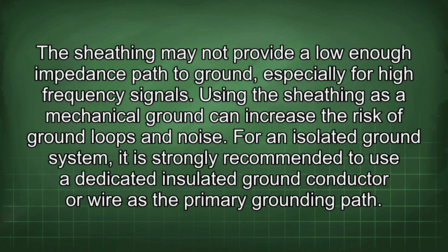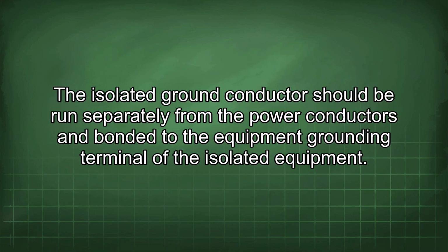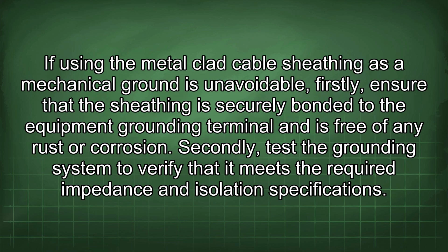For an isolated ground system, it is strongly recommended to use a dedicated insulated ground conductor or wire as the primary grounding path. The isolated ground conductor should be run separately from the power conductors and bonded to the equipment grounding terminal of the isolated equipment. If using the metal-clad cable sheathing as a mechanical ground is unavoidable, firstly, ensure that the sheathing is securely bonded to the equipment grounding terminal and is free of any rust or corrosion.